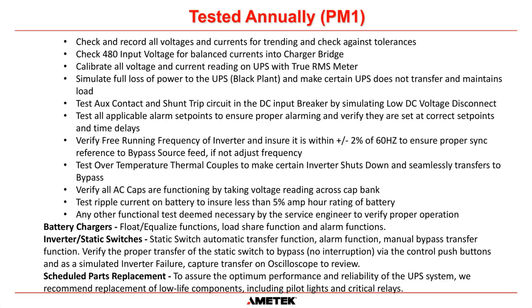We also calibrate all voltage and current readings on the UPS with respect to a true RMS volt or current meter. We use Fluke 87s and Fluke i410s. So we are making sure that whether it's analog meters or digital meters on the UPS itself, they are showing you exactly what the actual voltages are.